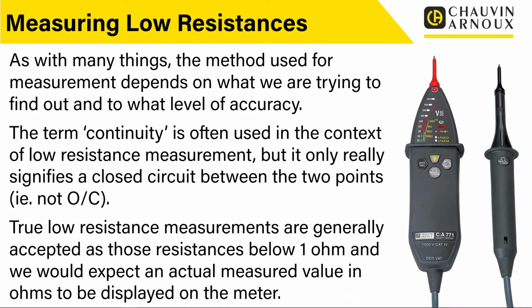True low resistance measurements are generally accepted as those resistances below 1 ohm. And we would expect an actual measured value in ohms to be displayed on the meter. So when we're talking about low resistance measurement, we can really rule out continuity measurements, because although sometimes we use the term continuity, as we said, this could be anything under 100 ohms in the case of this tester. So really, when we're talking about low resistances, we're talking about things that are generally below an ohm, often way, way, way smaller than that. An ohm is actually quite a big value when you look at micro ohms, when we're using micro ohm meters. So it is important to understand the context.